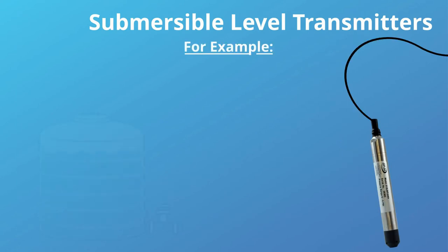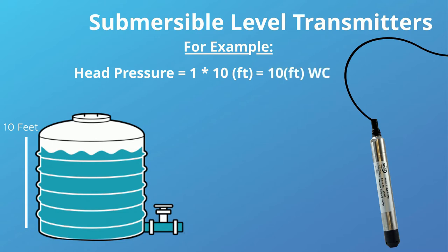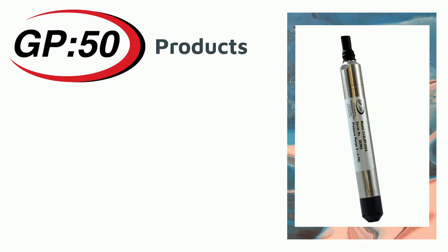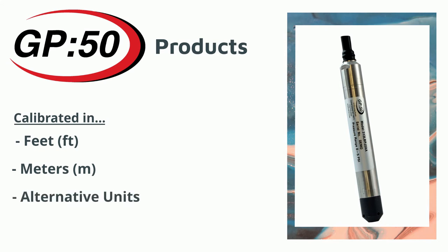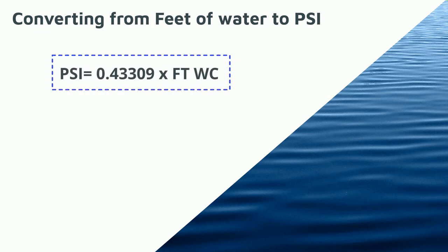For example, if we have a tank that is 10 feet tall and is filled with water, using the formula of head pressure equaling 1 times 10 feet, the water column is a hydrostatic depth pressure of 10 feet of water column. GP50 can provide a level transmitter calibrated in feet of water, meters of water, or any other alternative engineering unit, or we can provide units calibrated in pressure such as psi or bar. To convert from feet of water to psi, we use the formula: psi is equal to 0.433 times feet of water column.